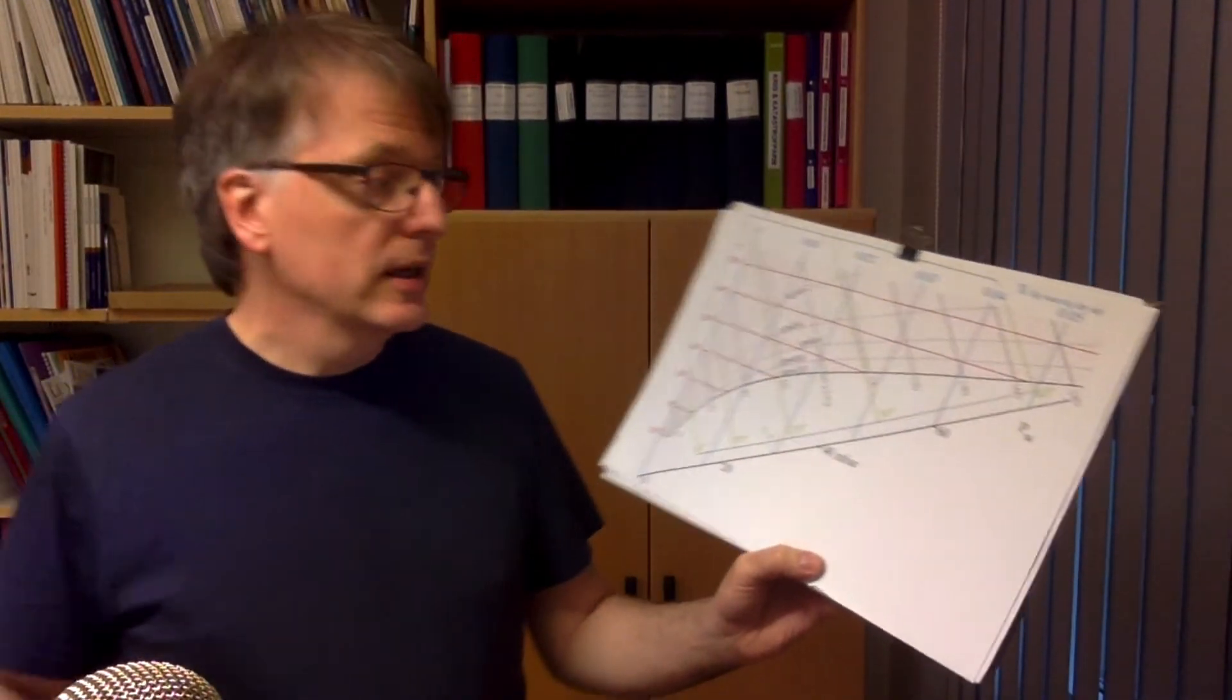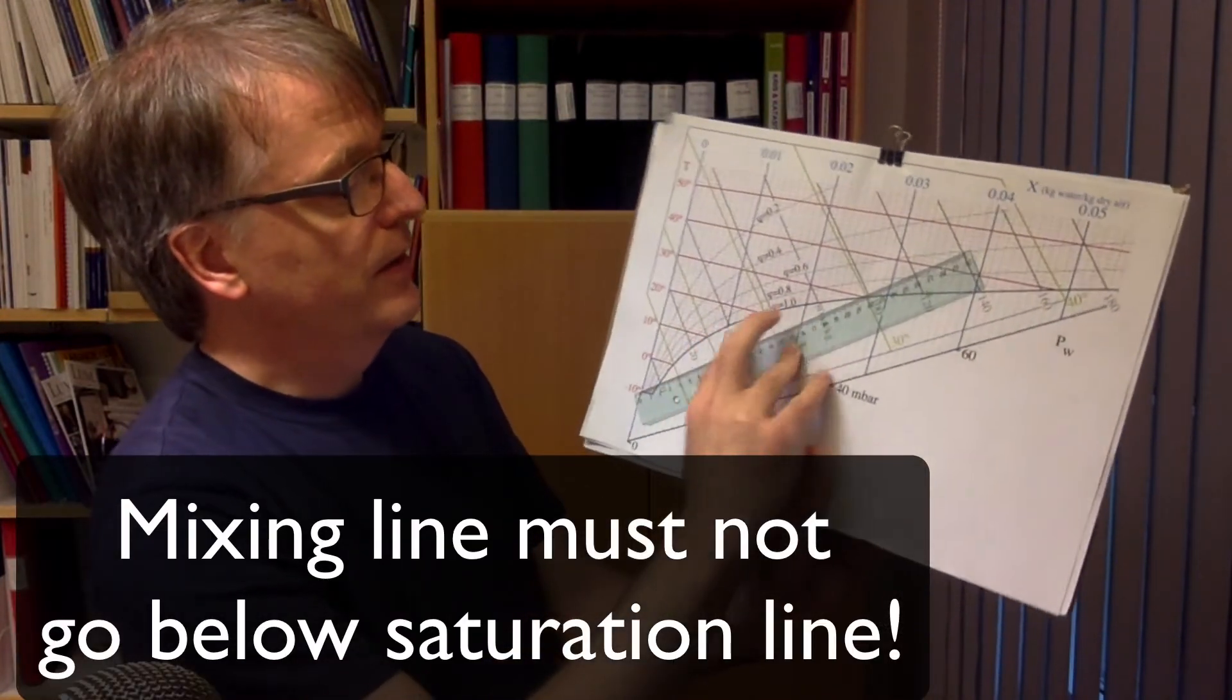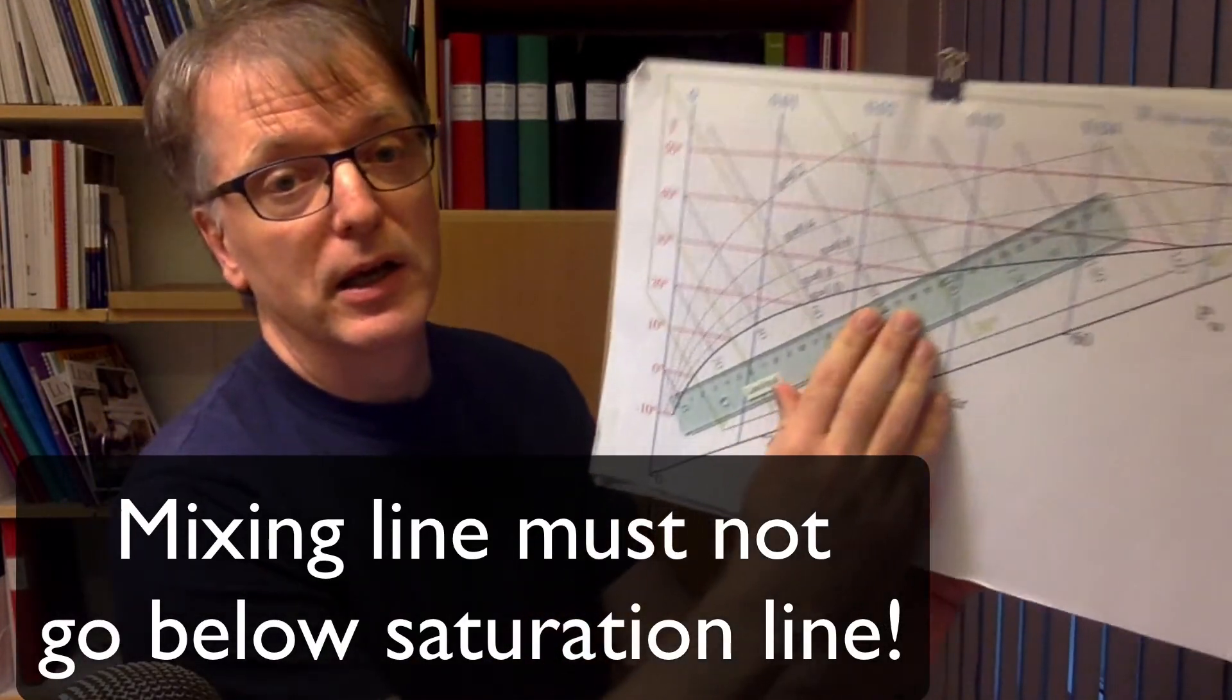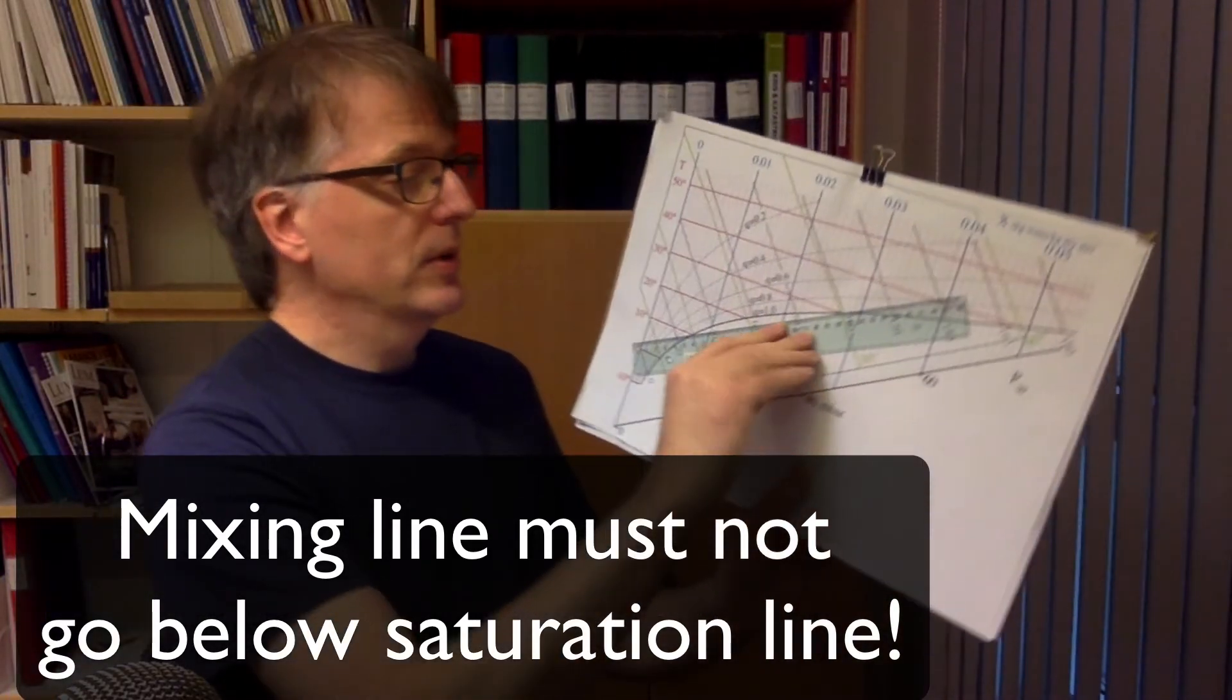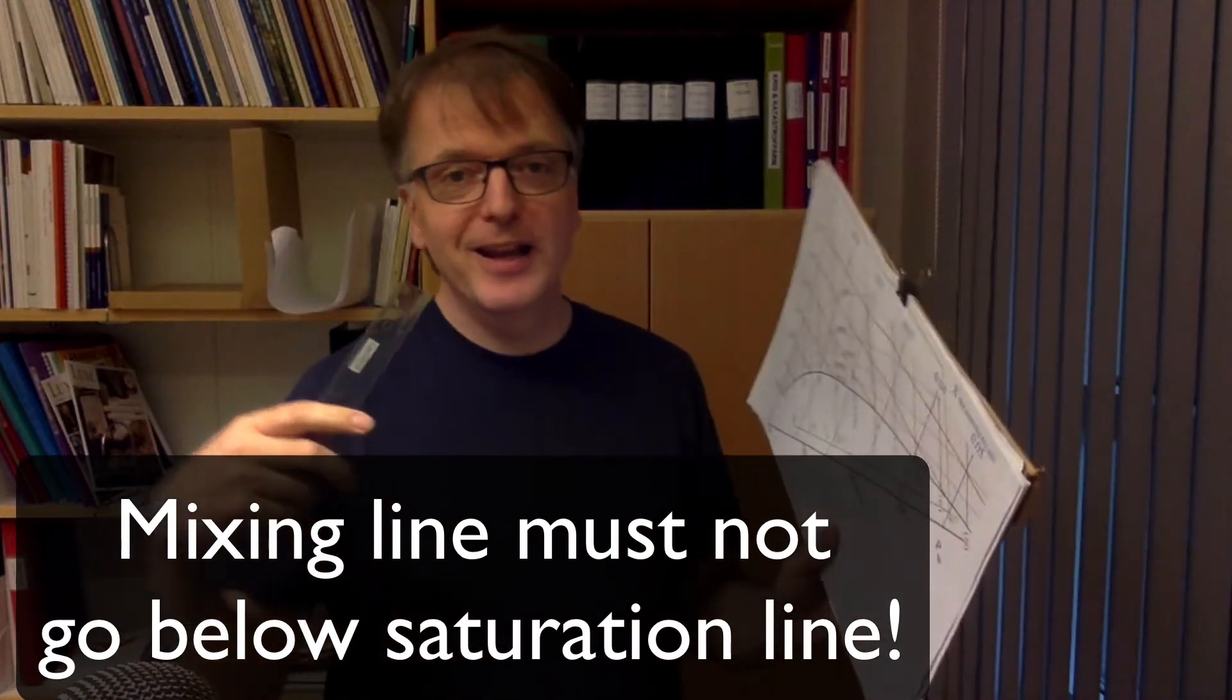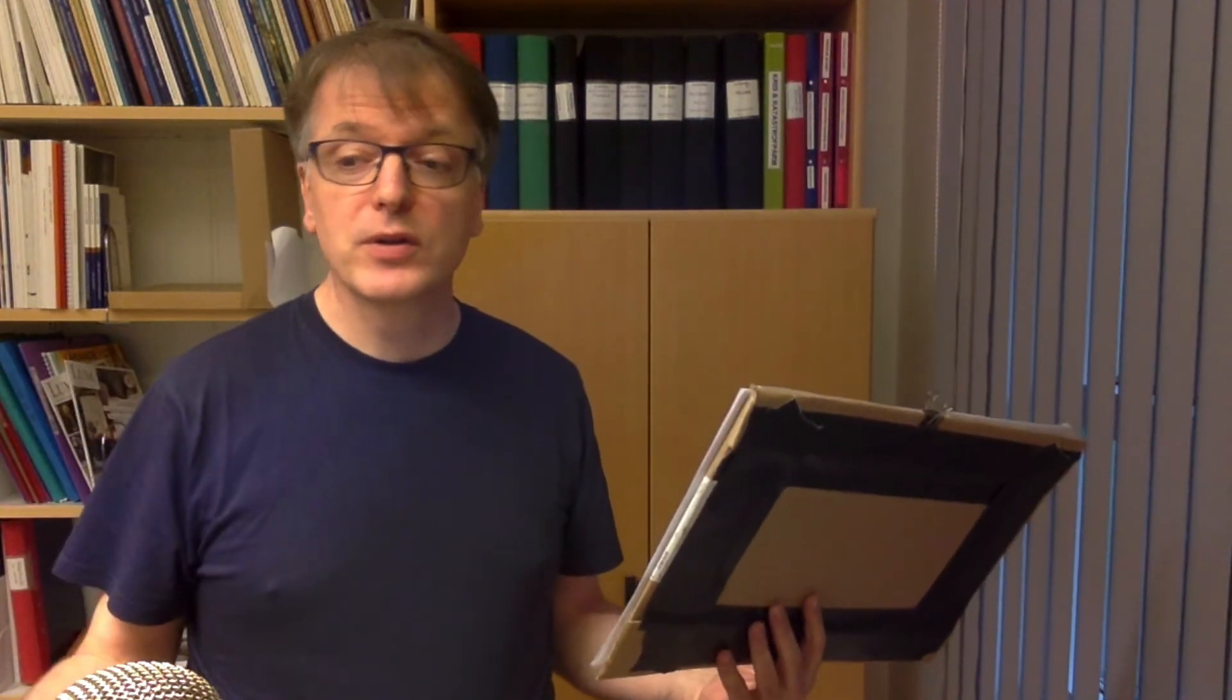An important thing here is that the mixing line should be above this 100% humidity line. So if the mixing line goes something like this then we're in trouble because then at certain mixture relations between the two air flows there is too much water and we will have condensation. And so if the mixing line goes below the 100% relative humidity line then we can't really be sure what happens.